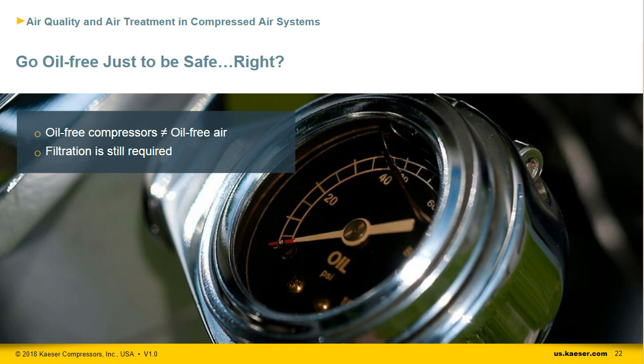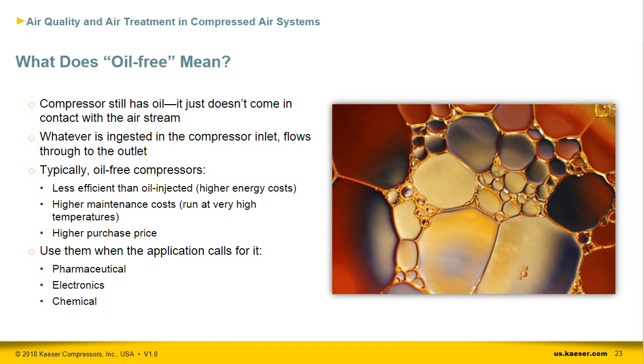What does it mean to have an oil-free compressor? It doesn't mean there's no oil in the compressor. It means the oil doesn't come in contact with the airstream in normal operation. Keep in mind whatever is in the ambient air will still be ingested into the compressor inlet and flow through the compressor. Filtration and drying are still necessary for clean, dry air and oil-free systems.